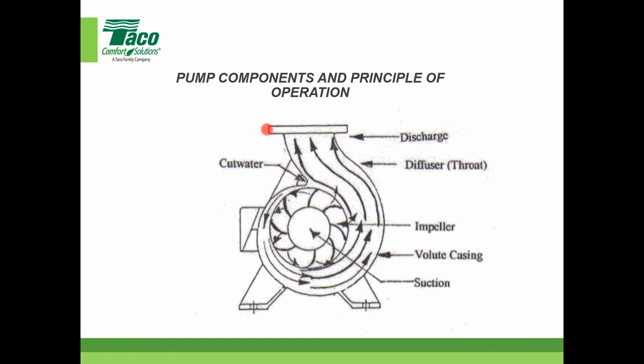In most of these centrifugal pumps, probably over 90%, 95% are flanged, right? So they have a flange arrangement on both the suction and the discharge. So let's see. Oh, by the way, at our facility, at Taco, after we've finished assembling a wet end pump, we pressure test it to 1.5 times the working pressure. And that's to make sure there is, we don't flow test. Pump manufacturers don't flow test. We are required to test our product lines, produce a family of curves, and then per HI, we have to hit that curve certain percentage, you know, and we do that.